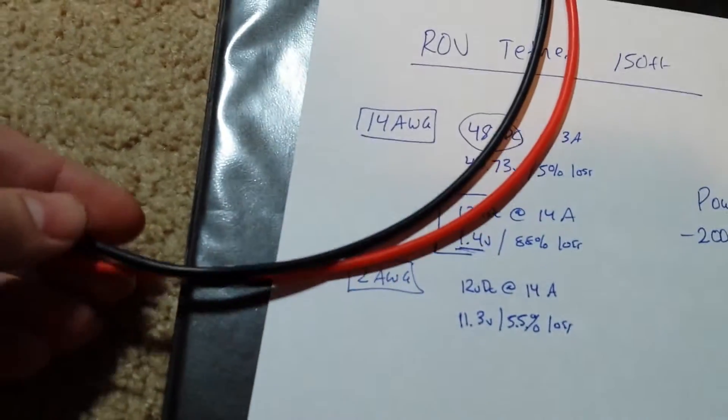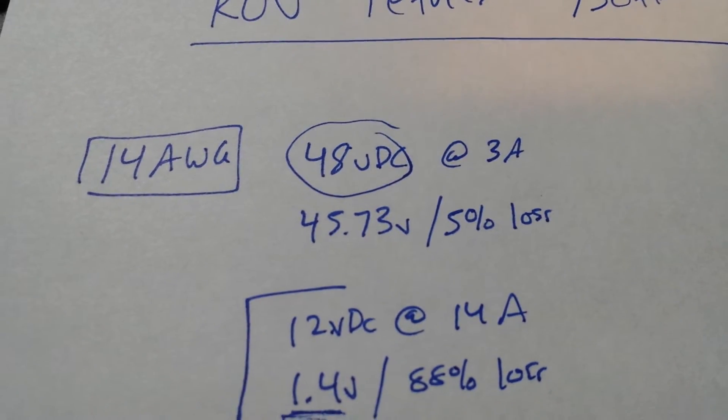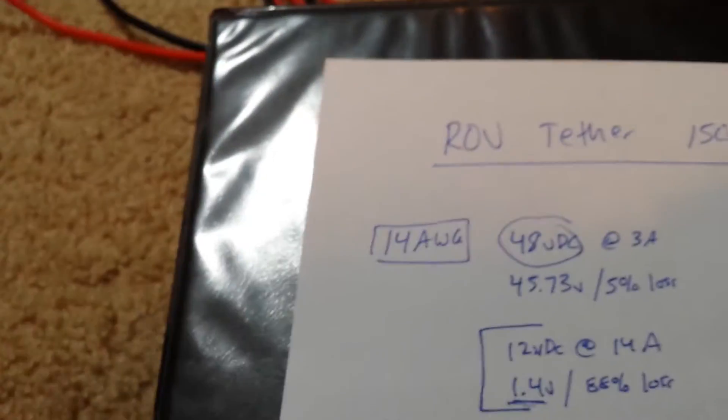I will use 14 gauge, maybe 12 gauge, just depends. And at the other end, when I'm drawing 3 amps there, I've only lost 5% of my voltage. So now, at the other end of this tether, I'm left with 45 volts at 3 amps. So now I gotta convert that down for all my motors.